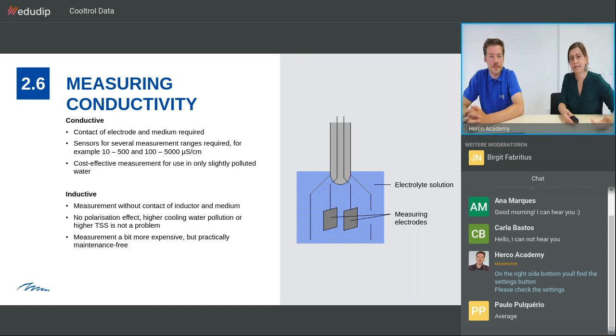Good. About conductivity, one more point before we wrap up the theoretical part. Conductivity can be measured in 2 ways, conductive or inductive. Our blowdown controllers, most of them work with both types of sensors. Conductive is the most common type and the more basic one, let's say. It requires several measurement ranges for low conductivity and high. And most important, it has a direct contact of electrode and medium.